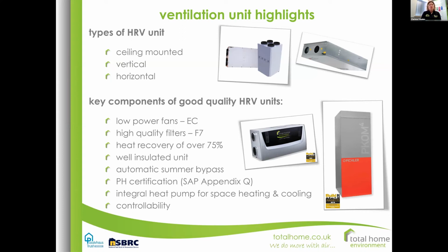Also having really high quality filters, F7 pollen filters, especially for those who have allergies or asthma, or if you're near arable land and stuff like that, they're very, very useful. If it's Passivhaus certified, then it will definitely have a heat recovery rate of over 75%. And do make sure that the unit itself is well insulated with at least 30 mil of insulation inside it to keep it at its own temperature.